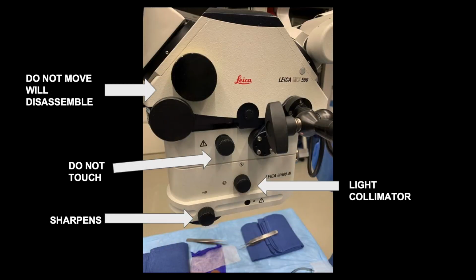There are a few knobs that we don't want to touch, and if you do touch them, they will disassemble the microscope. But 2 things on the side of the microscope are the light collimator and the sharpener. So the light collimator narrows down and cones down the light source so you can better see the surgical field. And also you can use the knob closest to the microscope to sharpen the image.